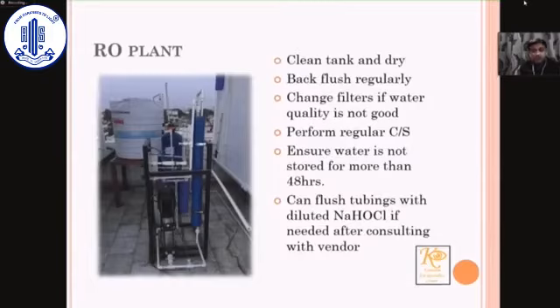It is also good practice to flush the PVC tubing that runs the water from the RO plant to the terminal UV filter with diluted sodium hypochlorite solution under pressure. This is usually done by your vendor on request. However, make sure that the tubings are flushed repeatedly so that there is no residual sodium hypochlorite left, as we might be using this RO plant to clean our instruments and also wash our hands.